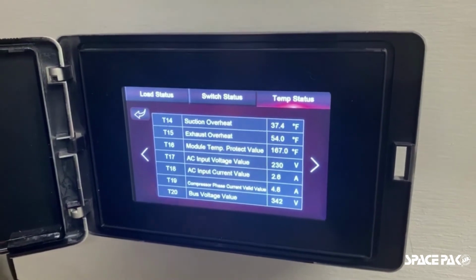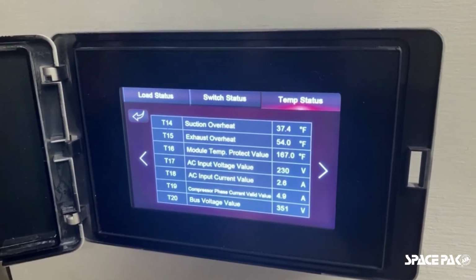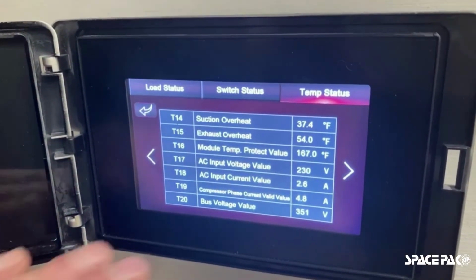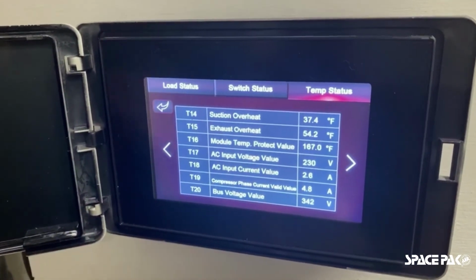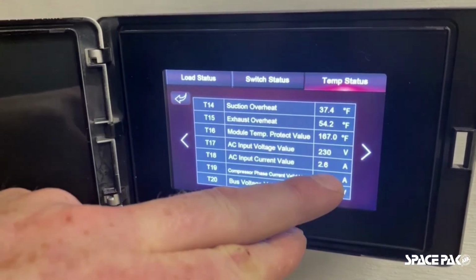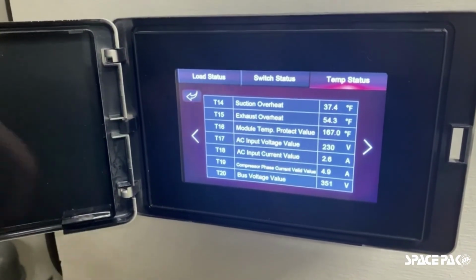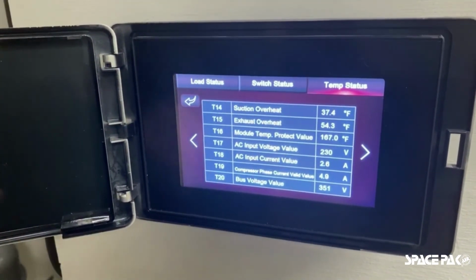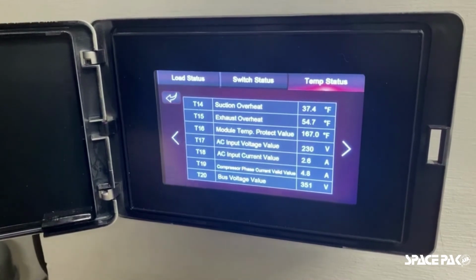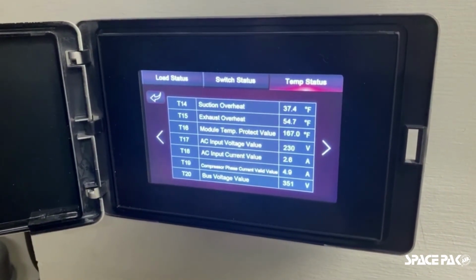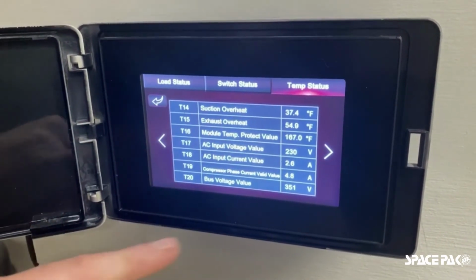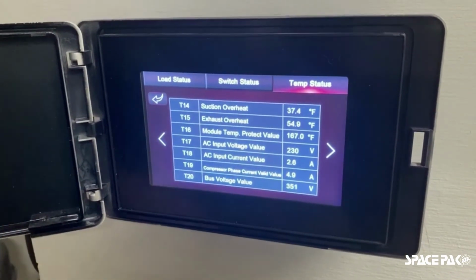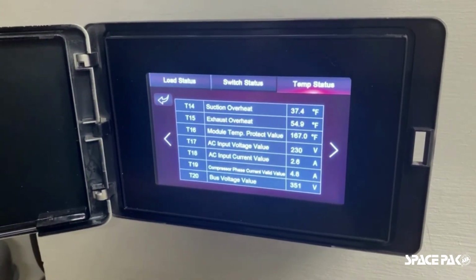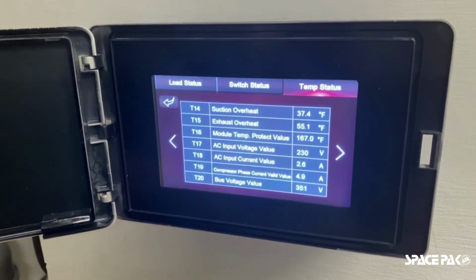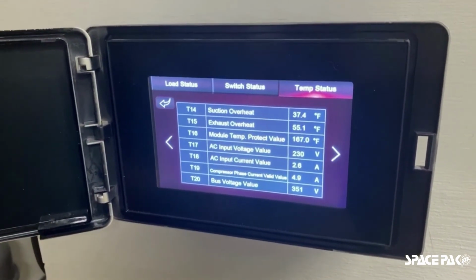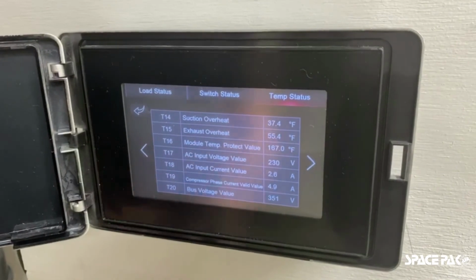One of the things that is really slick here is, we know our input voltage right now, this is real-time information. Our input voltage right now is, we're looking for 230 volts, and that's what we're getting. Our current amp draw of the unit, so this would be in place of necessarily putting your own amp clamp on the system. It shows you right here, this unit, current running state at 30 hertz, is pulling 2.6 amps of electricity. Okay, really great information for you to just look at on the fly.